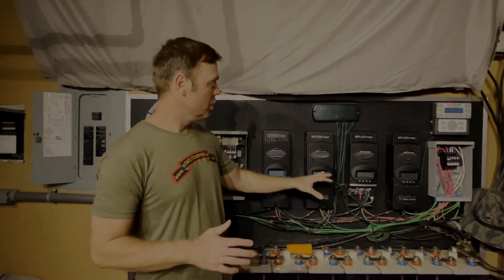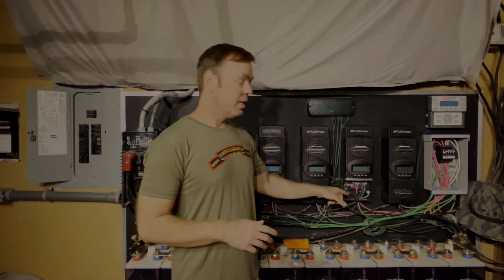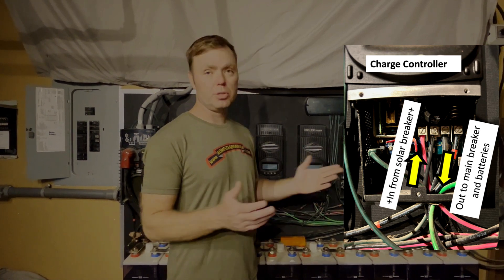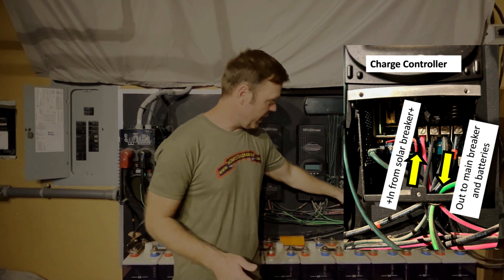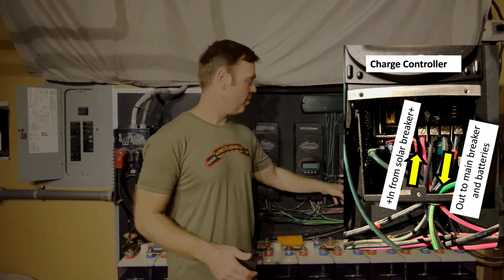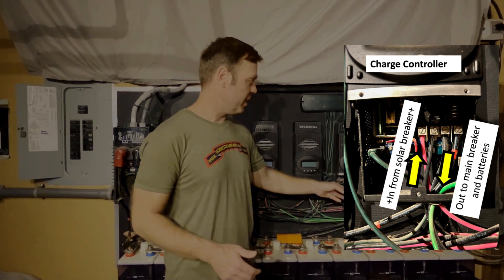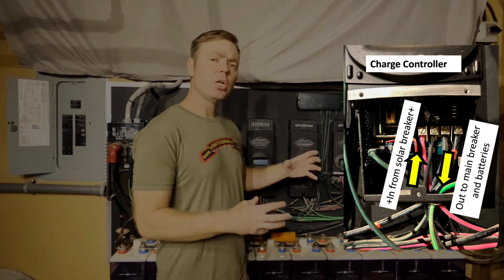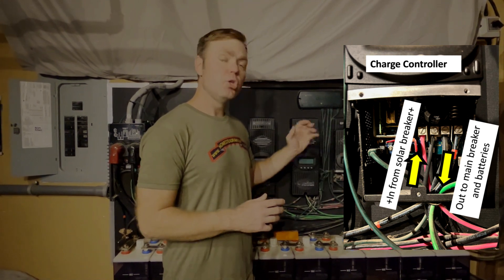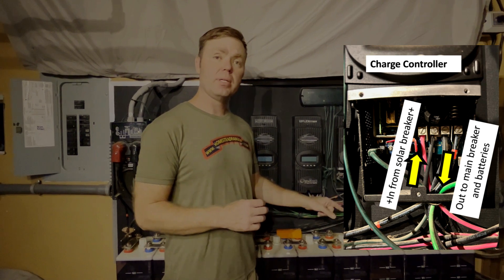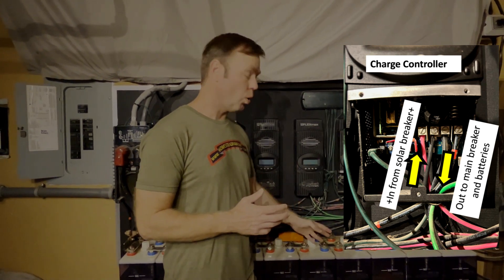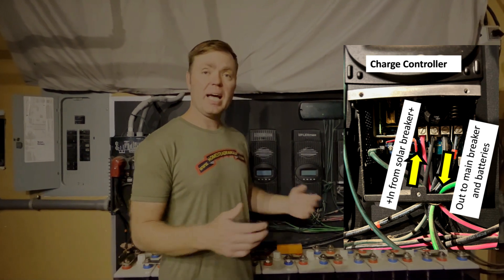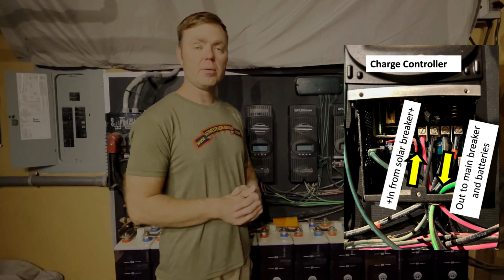We went from the solar panels to the charge controller. The negative wire goes into the charge controller directly, and the positive wire goes through the circuit breaker and then into the charge controller. In the charge controller, there's an in for the positive and an out for the positive, an in for the negative and an out for the negative. Your charge controller is going to take that voltage, which is variable coming from your solar panels, and turn it into the exact voltage and amperage that you need to optimally charge your batteries. Based on what type of batteries you use, you can program it for a lithium-ion battery, a lead-acid battery, or in this case, we have nickel-iron batteries.